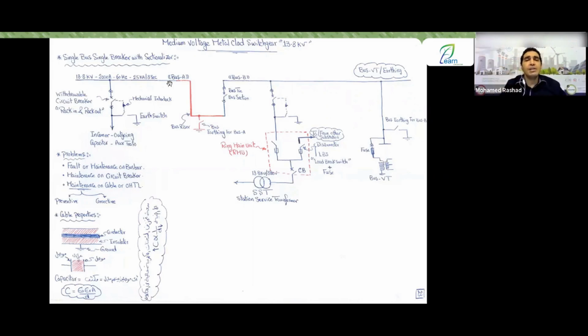You can isolate the breaker and work on the cable without any issue. Of course, you might have another problem, but in terms of capacity with the charges, they said, what should we do? They said, okay, it's very simple. Instead of the station being just a single connection, which is only one bus bar that everything is connected to, I can divide it into one bar and another bar, meaning I can divide it into 2, 3, or 4 bars. For example, in this station, I have 3 power sources and 17 feeders going to supply different loads, regardless of what they are. So in total, I have 20 feeders, right?